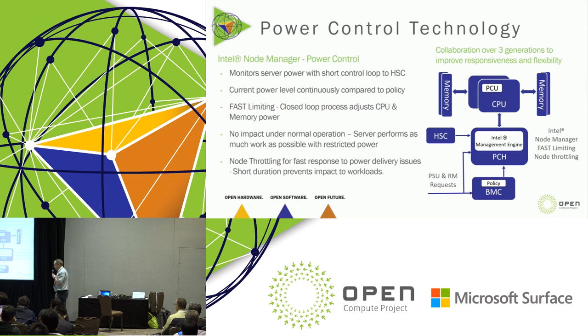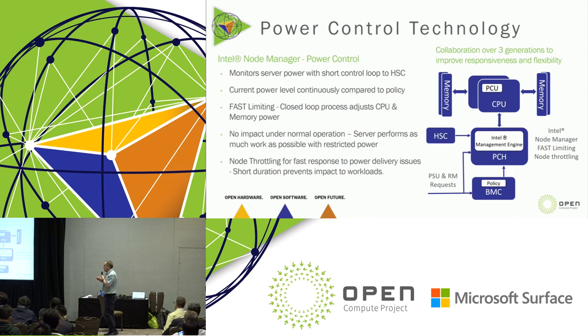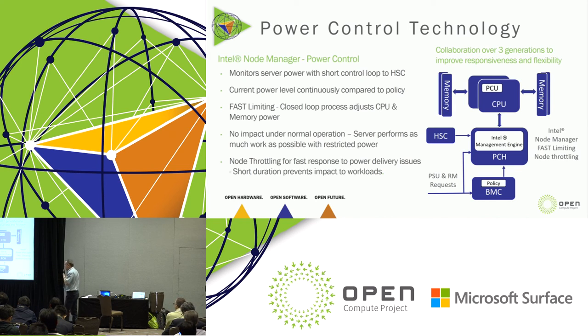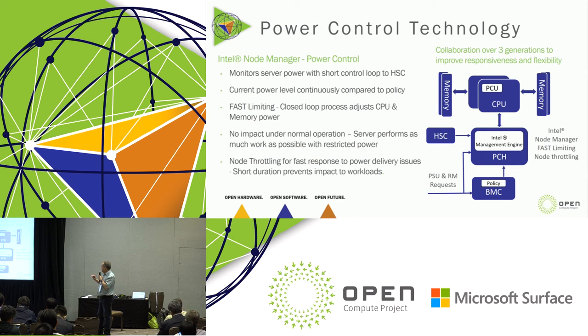Another thing we have to handle is unexpected rises in application load or some kind of power event where you need to very quickly throttle the CPUs or the whole node to respond. That's where requests come in directly from power supplies or the rack manager. Intel Node Manager will work with the CPUs to, in just a few milliseconds, drop power quickly and ramp up to a new default power cap at a lower level than the previous cap. A lot of effort is put in to make sure this is done in a smooth and incremental method that does not impact applications.